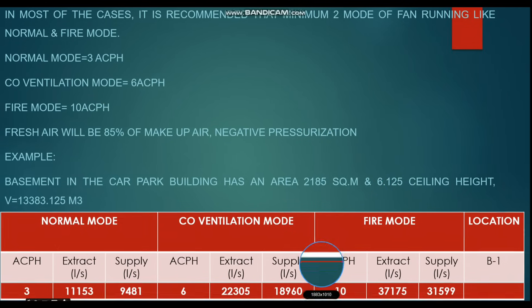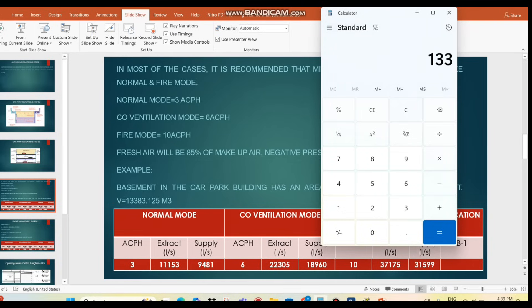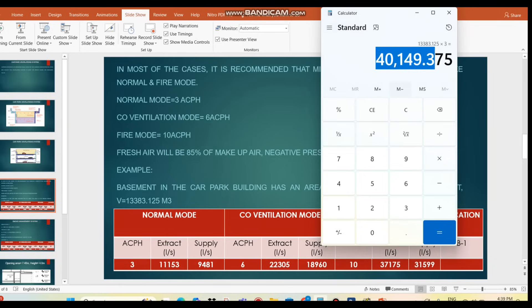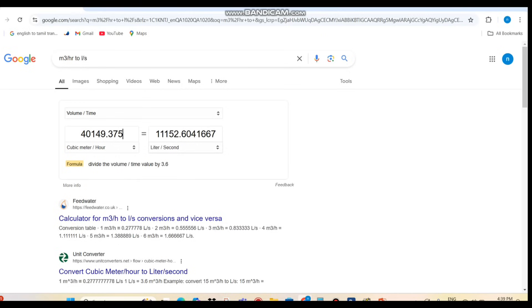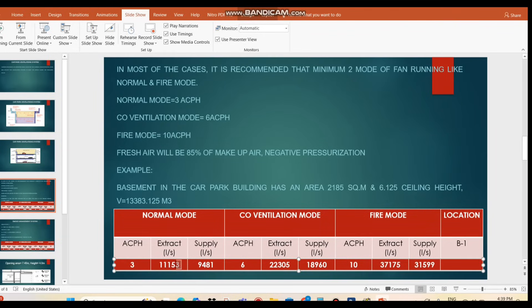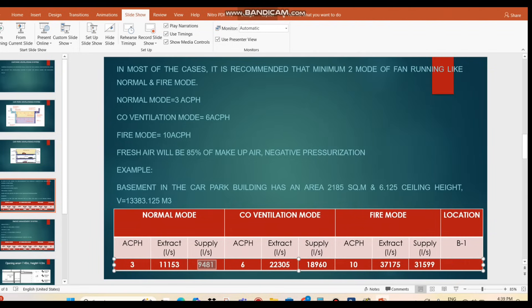For the normal mode at 3 ACH: total volume 13,383.125 m³ multiplied by 3 gives the result in cubic meters per hour. Converting to liters per second gives approximately 11,153 L/s for the exhaust fan flow. For the supply (makeup air), we consider 85% of the exhaust to maintain negative pressure, so 11,153 × 0.85 gives approximately 9,480 L/s as the normal mode supply air flow.